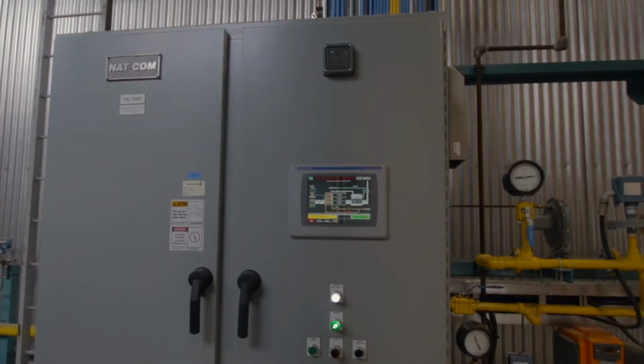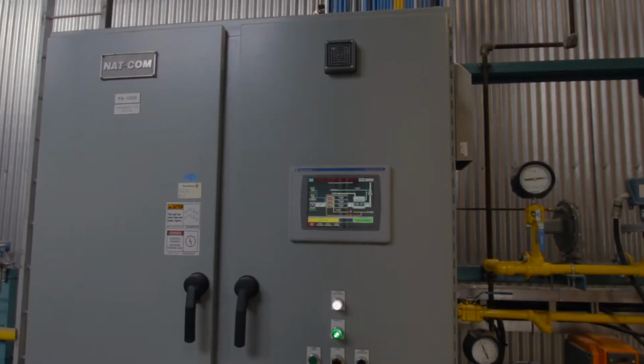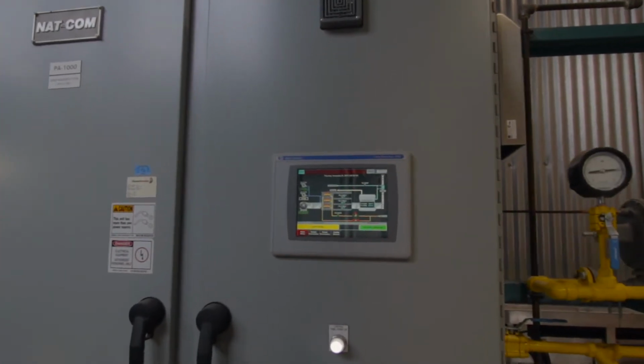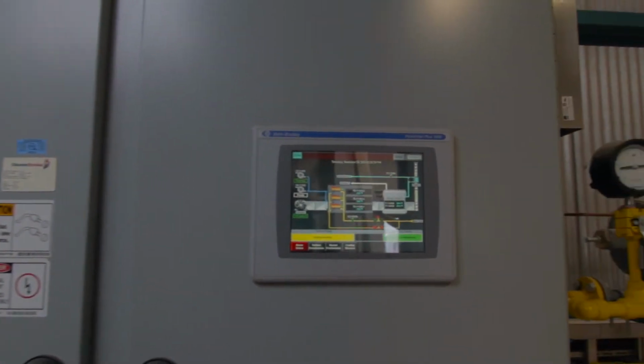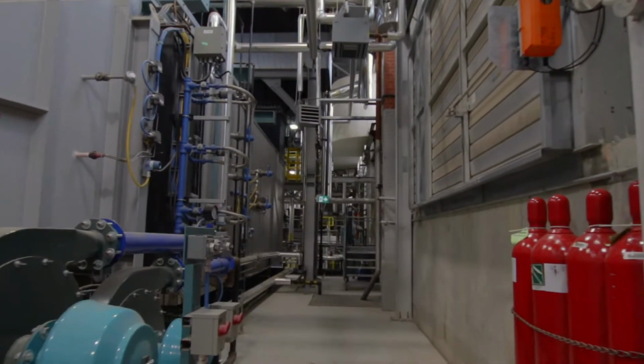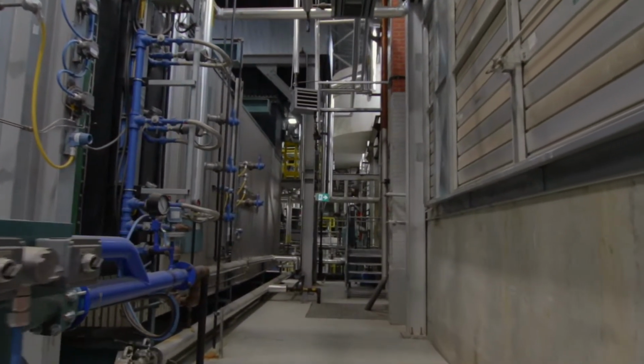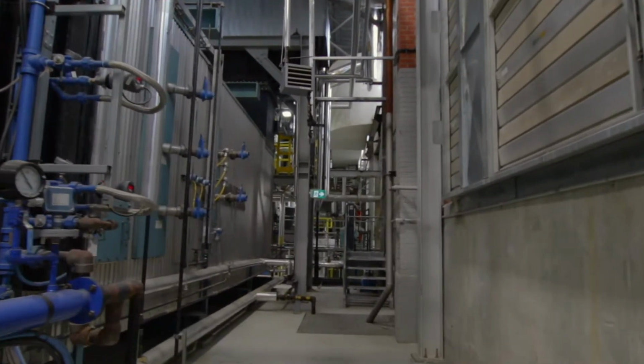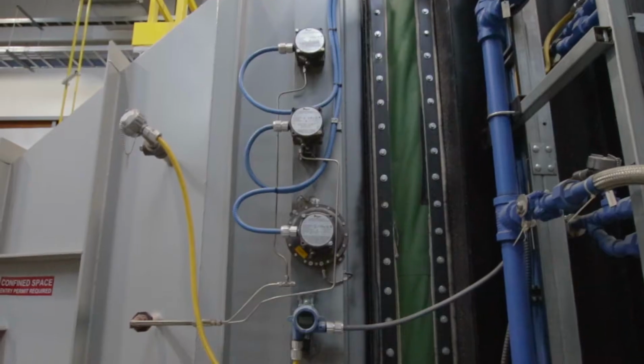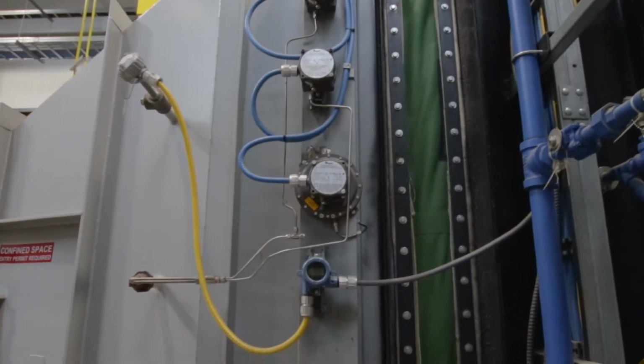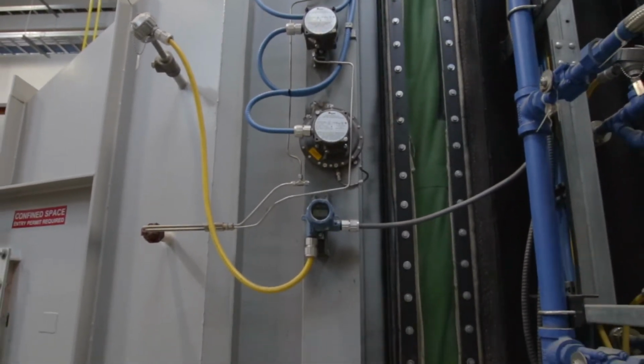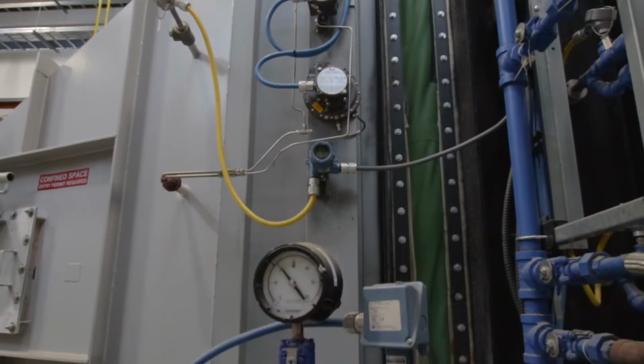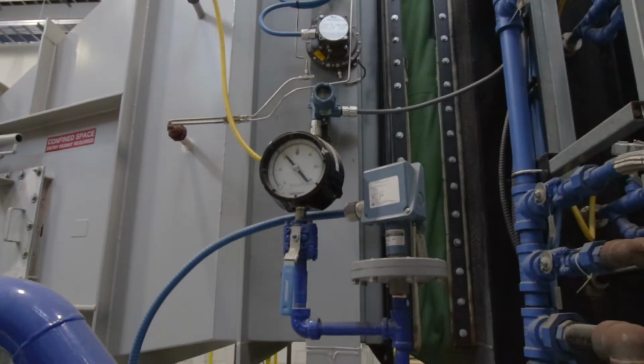It's equipped with a Natcom duct burner, and so the unfired rating, if there was no gas being burned in the duct burner, is about 25,000 pounds an hour, and then the duct burner will increase the gas temperature such that we can get up to 90,000 pounds an hour of steam out of the system. It's also equipped with a feedwater economizer that makes the overall system more efficient, and then it has all the boiler trim and feedwater control, natural gas control, steam metering, all the bells and whistles that go around it that contribute to a highly reliable and highly efficient system.